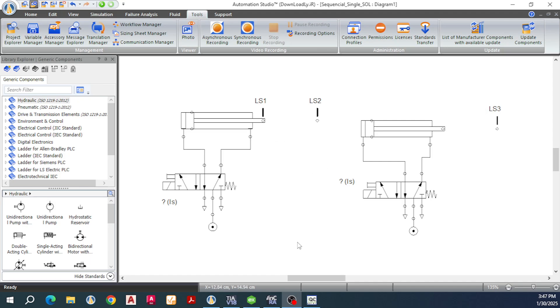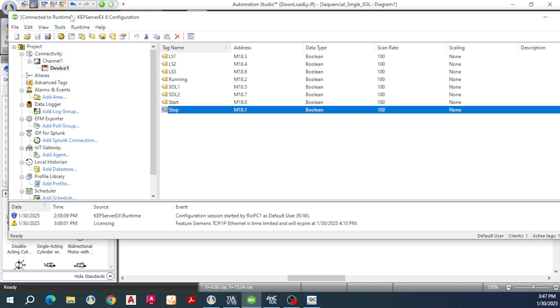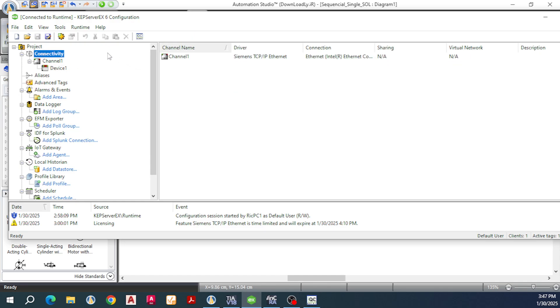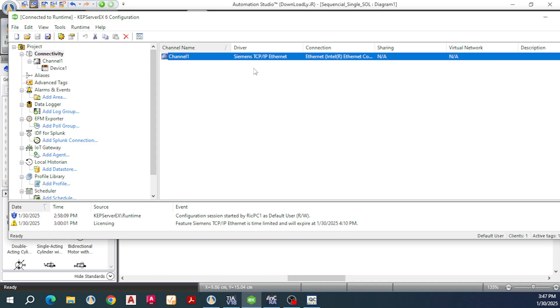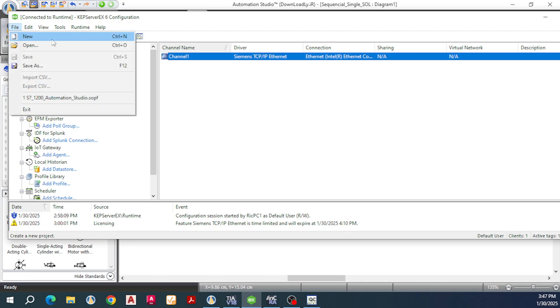First, your computer must have a KEP server. In my case, I have installed KEPServerEX6. The first step is to create a channel. In my case, I created channel number one and the driver for that is Siemens TCP/IP Ethernet. You can do that by going to File and then creating new.